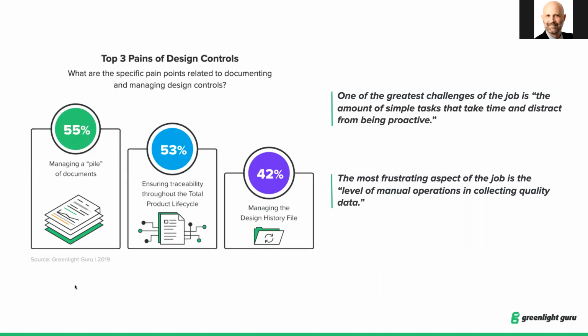That's a big challenge. Another one is that this concept of traceability, design control traceability, is so key, because from the very beginning you're trying to solve some sort of clinical issue or problem. From there, you start to define things like user needs, and then expand upon that into design input requirements, and then you have outputs, and then you're going to do verification and validation. Well, you need these things to be linked and traceable, and you need to have this closed loop traceability from a design control perspective, so that you know what you've been doing, how things are related, what the flow of information is. Very important to do.